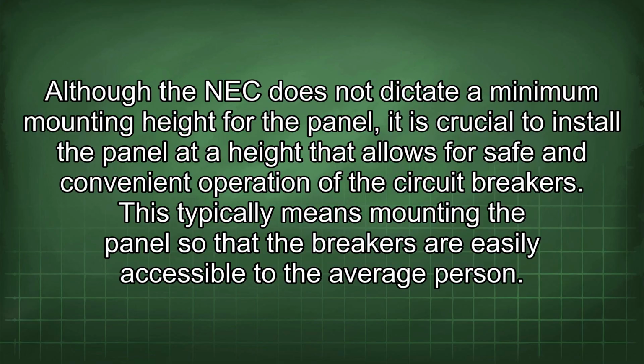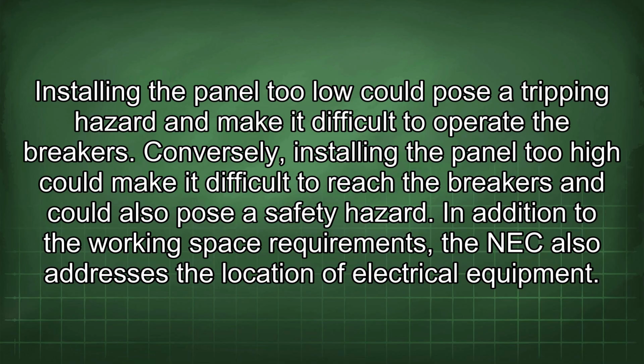Although the NEC does not dictate a minimum mounting height for the panel, it is crucial to install the panel at a height that allows for safe and convenient operation of the circuit breakers. This typically means mounting the panel so that the breakers are easily accessible to the average person. Installing the panel too low could pose a tripping hazard and make it difficult to operate the breakers.